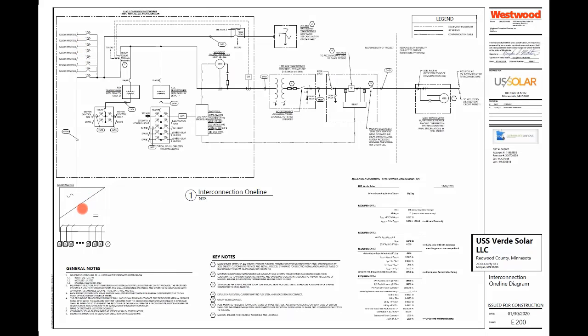Here we have a string inverter, and this is our 1 to N inverters, depending on how many you want. That inverter feeds up to group mounted 175 amp thermal mag circuit breakers. So that's where our AC paralleling is occurring at the switchboard level. The switchboard has no metering between those group mounted breakers necessarily and the main disconnect breaker. So that 1600 amp breaker is the disconnect out to the utility. They instead have the customer metering and utility metering between the main disconnect breaker and then out to the transformer and up at the medium voltage level.